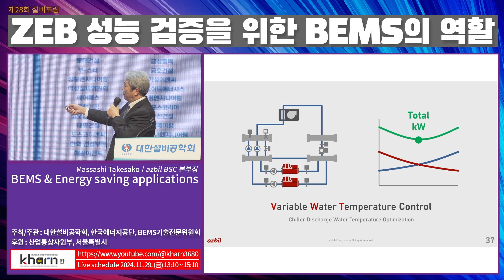But do we need to do that? Do we need to maintain 7 degrees at all times? This is the question. So anyway, this variable water temperature control is to change the chiller leaving water temperature according to the load demand, together with the condenser water pump consumption. This is what we are now promoting. Once we change the supply water temperature to be higher, meaning from 7 degrees to 8, 9, 10 degrees, the chilled water volume will increase. This is a trade-off. So when the supply water temperature becomes higher, the chilled water pump power consumption will be higher also. So we need to find the best operating point.